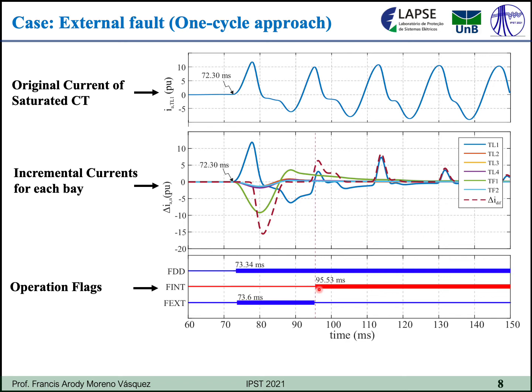With a half-cycle approach, the only signal which must have an opposite polarity in relation to the rest corresponds to the faulted feeder. All the others, including the differential signal, must have the same polarity, but this does not occur with the one-cycle window, which changes polarity and becomes equal to the polarity of the initially faulted feeder, and that would represent an internal fault, or the evolution of the external fault to an internal fault, and in this case it is wrong.